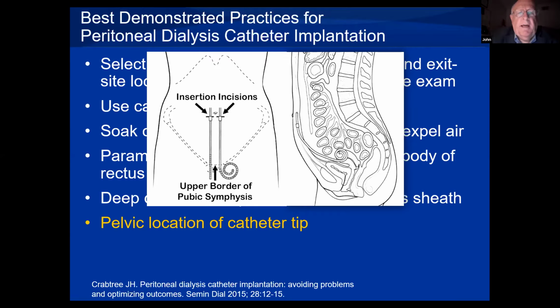So how do we avoid having the catheter tip implanted too deep in the pelvis? What landmarks do you use? Well, unfortunately, if you use the umbilicus as a landmark and you're using a midline infraumbilical approach, that does predispose to the catheter being implanted too deep in the pelvis if you haven't taken into account the dimensions of the catheter tubing. So what we found useful, if you're using a coil tip catheter, is aligning the upper border of the catheter coil with the upper border of the pubic symphysis bone while the patient's lying completely flat and marking the upper border of the deep Dacron cuff. That's where you'll make the skin incision to intercept the musculofascial layer at the proper distance above the pelvis, so that the end of the catheter tip is actually in the upper part of the true pelvic bowl. If you're using a straight tip catheter, we take 0.5 centimeters from the tip of the catheter, and that's what we align with the upper border of the pubic symphysis.